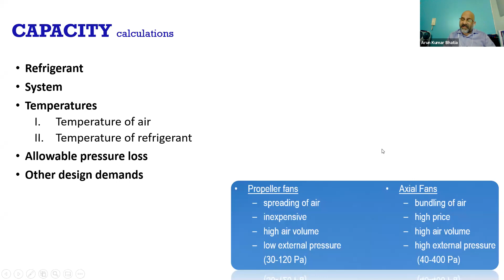There are propeller fans and axial fans which generate different air volumes and pressures. Another important factor for evaporator selection is how long your room is. For example, if my room is 50 meters long, my evaporator fan will be different. But if my room is 10 meters long, my evaporator will be different. The air throw of an evaporator will be different.